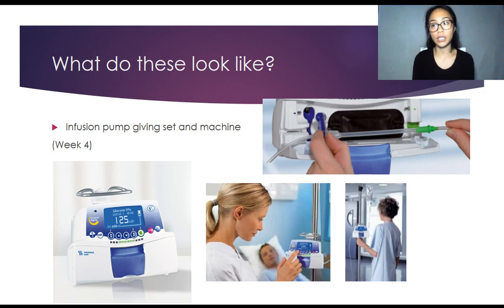And that's the risk that is run when you have a gravity infusion set. There's nothing to detect the presence of air in the line, except usually the nurse, to visualize that there is air in the line, stopping the infusion and eliminating that air before any infusion can continue. And that's dangerous because it can create an air embolus.